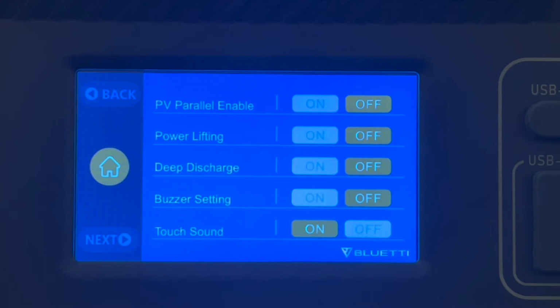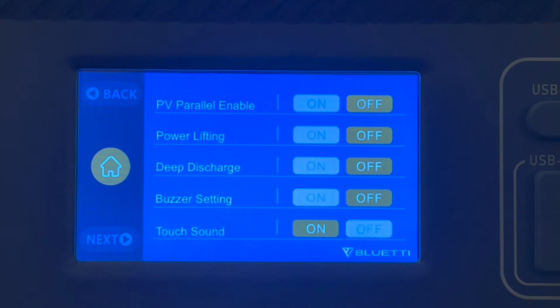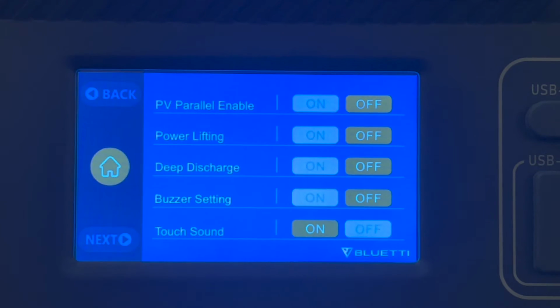So let's say you have one solar array that gives you 100 volts output, and you've got 10 amps on that one. And you've got another solar array that gives you the same 100 volts output, but that solar array is set up so that you have 20 amps. If PV parallel was turned off, one controller would give you 10, the other controller would give you 15, because the controller's maxed out at 15. So you're going to lose 5 amps that you actually technically have enough capacity for.